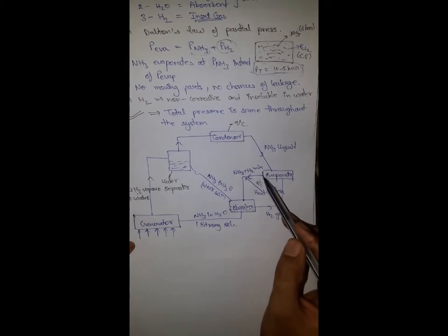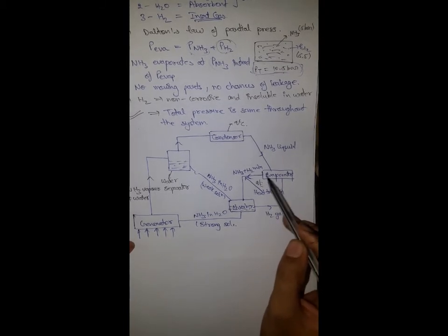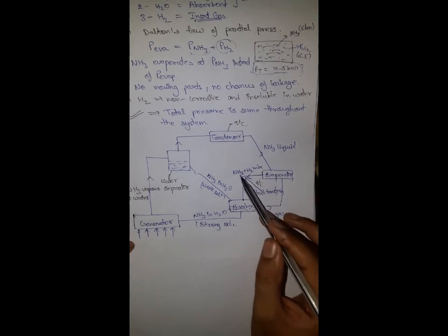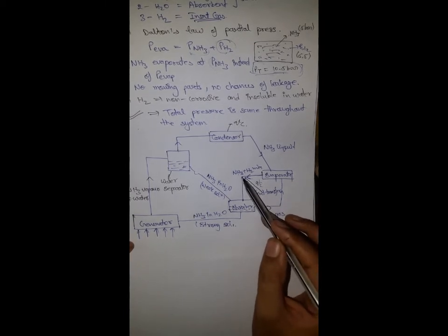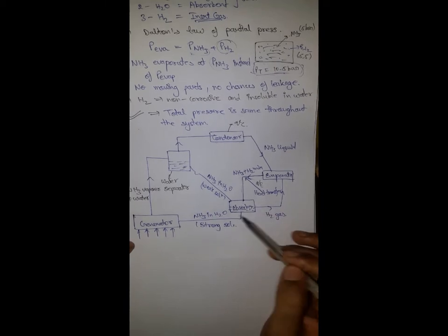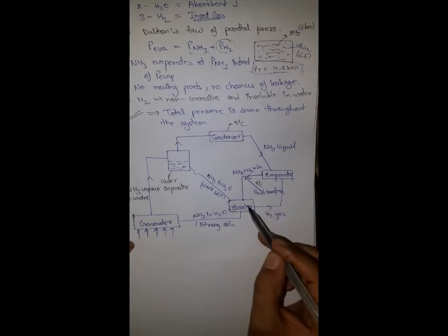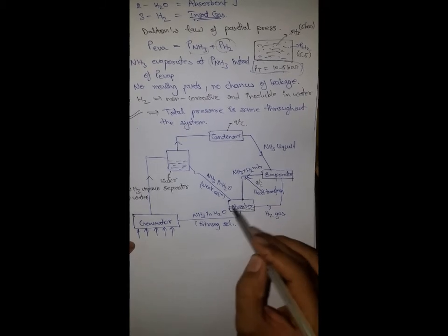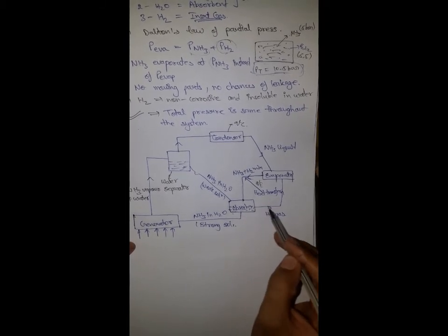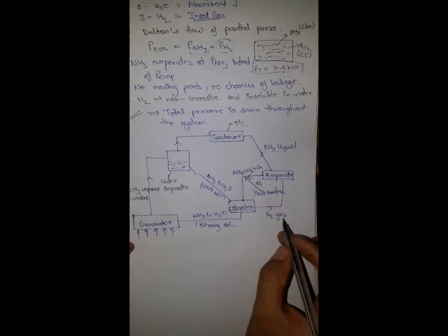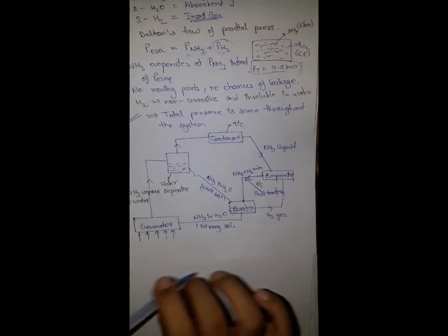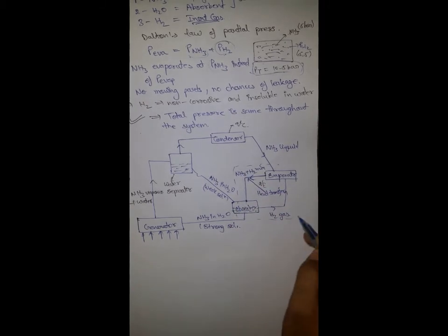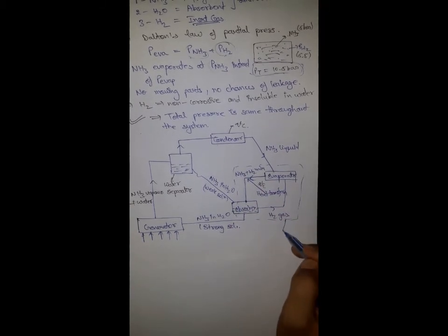So it gets evaporated, and refrigeration is done, and this ammonia and hydrogen mixture then circulates back to the absorber, and as hydrogen is insoluble, it does not dissolve in the water, so hydrogen gas is circulated back to the evaporator. So hydrogen gas is confined only to the evaporator and absorber space. It does not move to any other space. This is the hydrogen confinement.